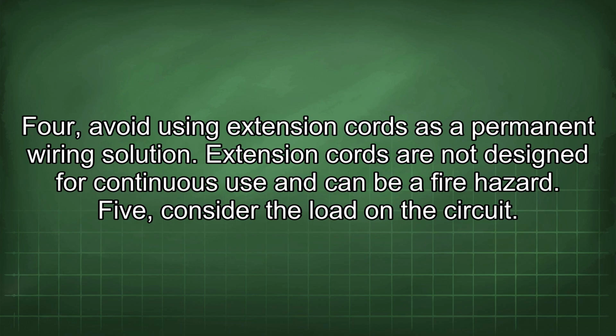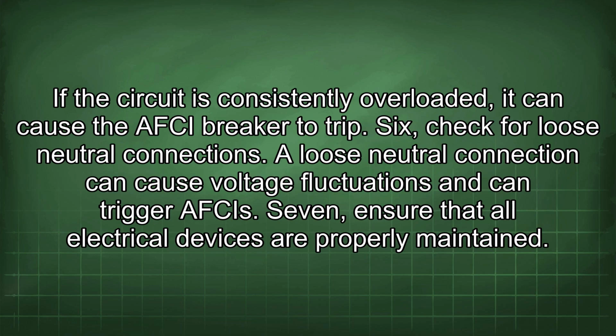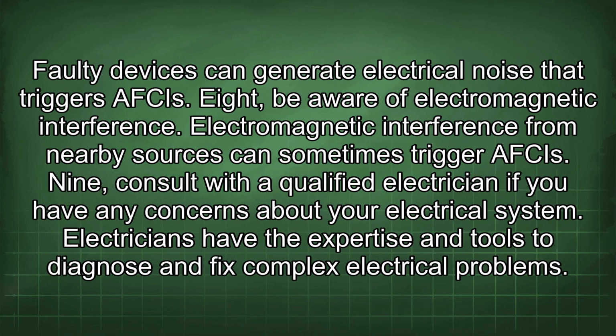4. Avoid using extension cords as a permanent wiring solution. Extension cords are not designed for continuous use and can be a fire hazard. 5. Consider the load in the circuit. If the circuit is consistently overloaded, it can cause the AFCI breaker to trip. 6. Check for loose neutral connections. A loose neutral connection can cause voltage fluctuations and can trigger AFCIs. 7. Ensure that all electrical devices are properly maintained. Faulty devices can generate electrical noise that triggers AFCIs.